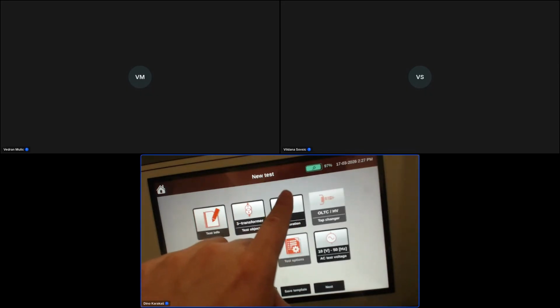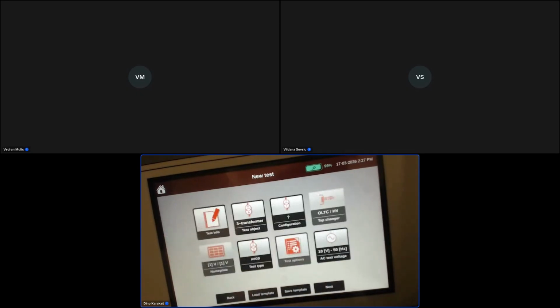So you can select the test object, as this is the three-phase transformer. We will proceed with that. Configuration of device can be selected, and as I already said, we can go with automatic vector group detection. It's listed here in tests. We will press automatic vector group detection, press confirm, and select the test voltage. Test voltage, as previously said, can be one of these values. Because this is the smaller transformer, we can go with 10 volts here.